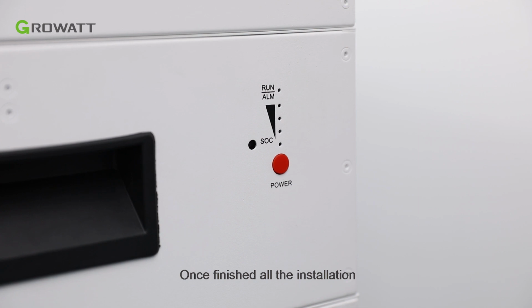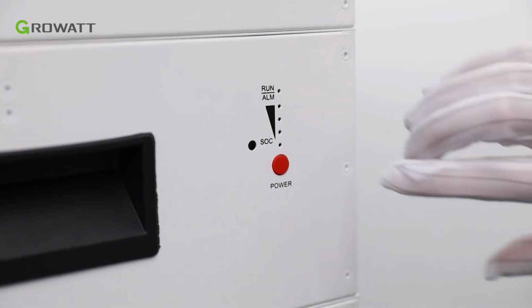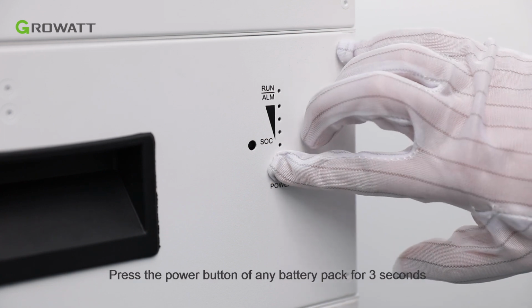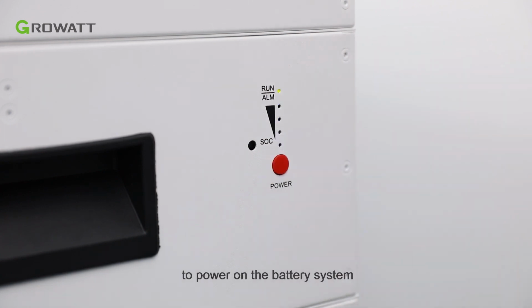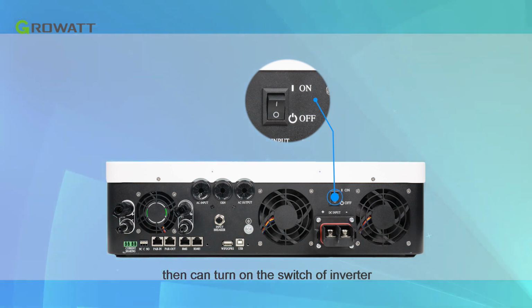Once all the installation is finished, the next step is to power on the whole system. Press the power button of any battery pack for 3 seconds to power on the battery system, and the SOC indicator will flicker for a short time and finally stay on. After the battery system is powered on, you can turn on the switch of the inverter.